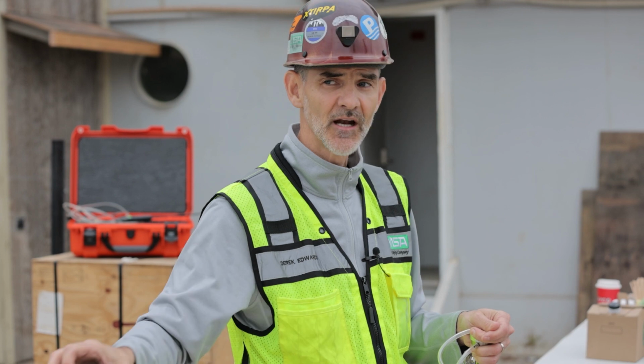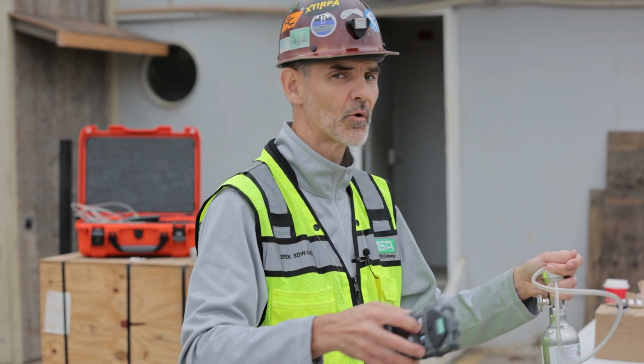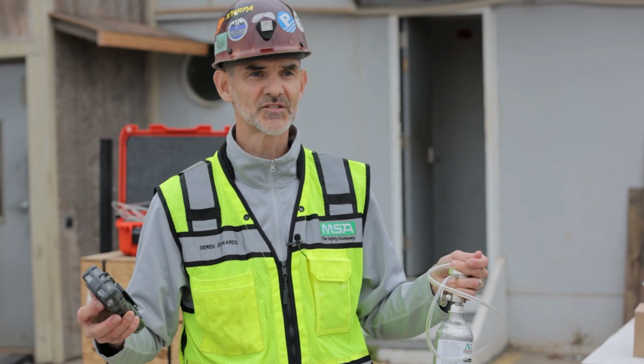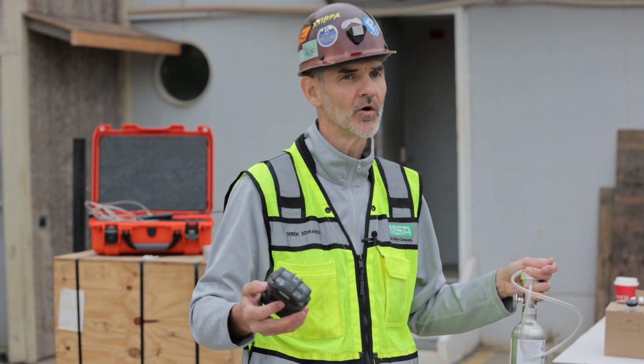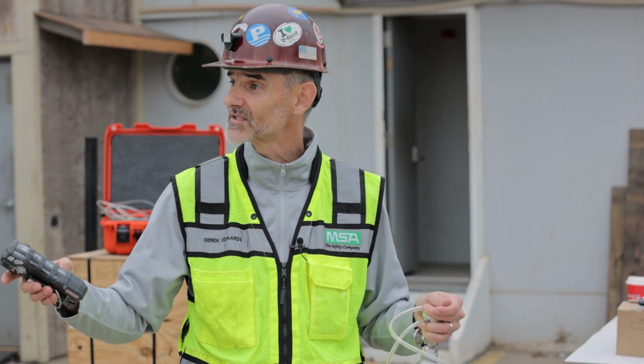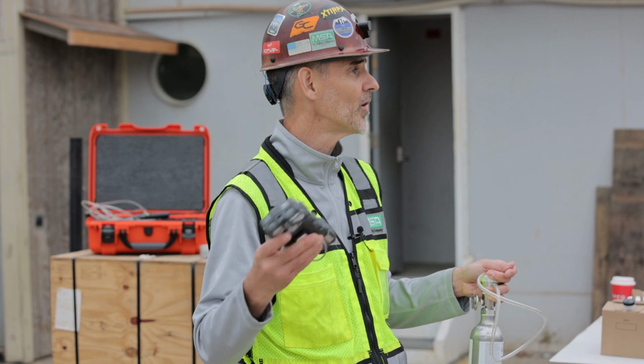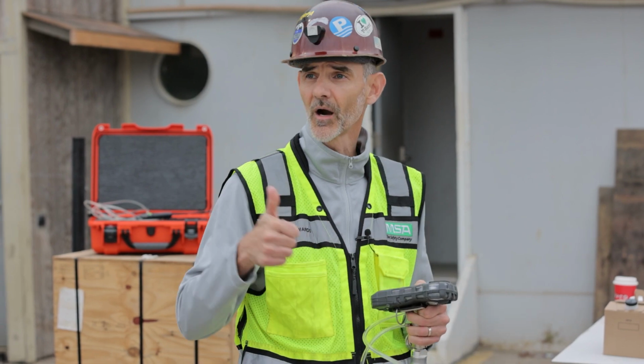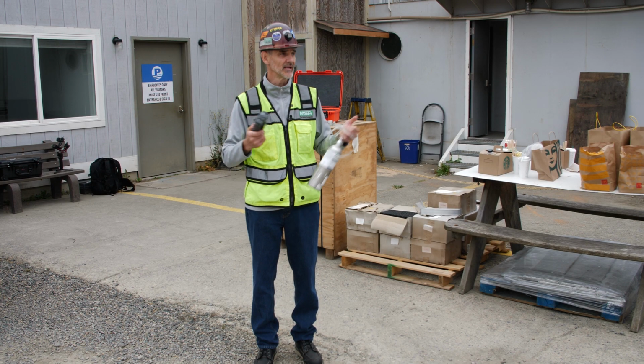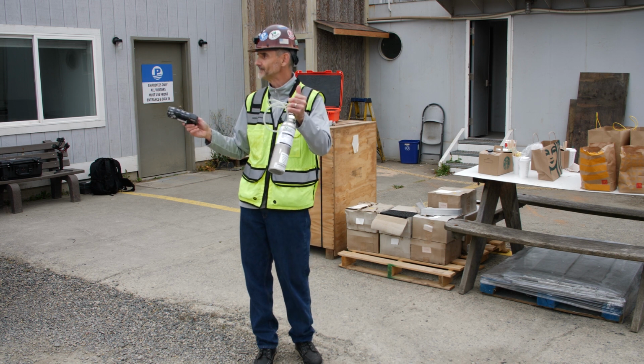So if an instrument's sitting on the table, you walk in, hey, we're ready to go to work. Has this instrument been bump tested? I don't know. It's really easy. Look at the top of the screen. There's either a check mark there or it's not. Check mark, use it. No check mark, it needs to be bump tested just like I showed there.